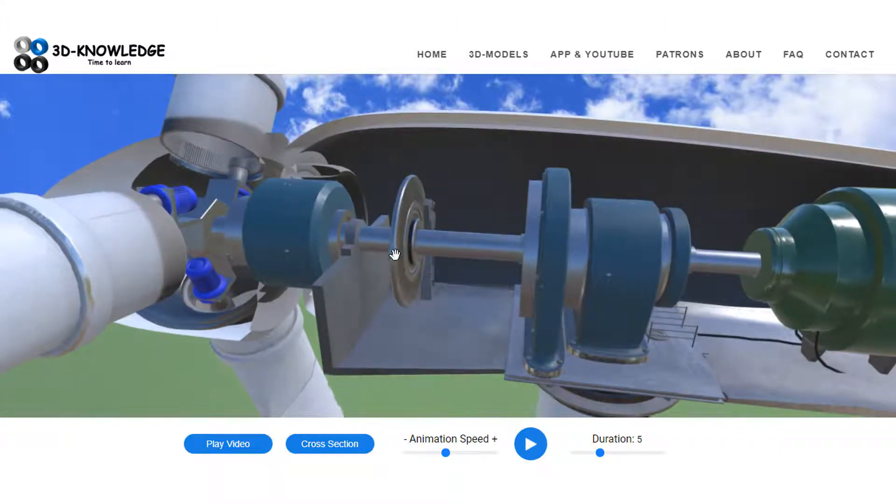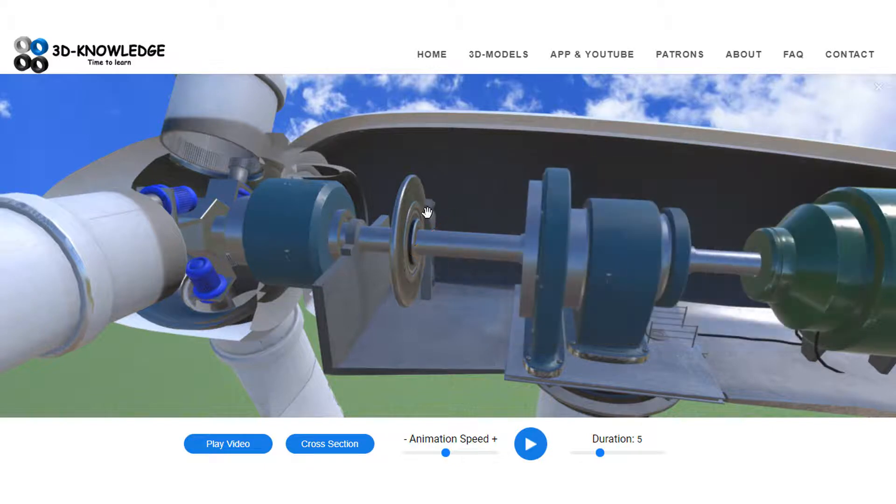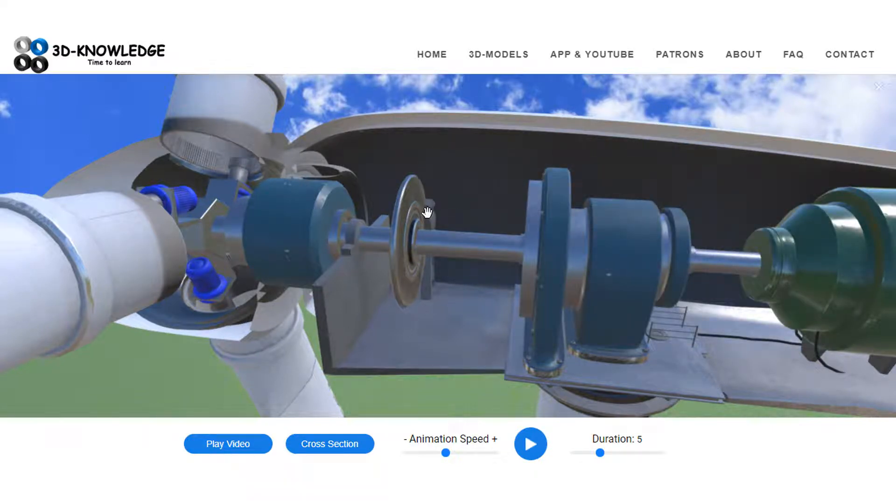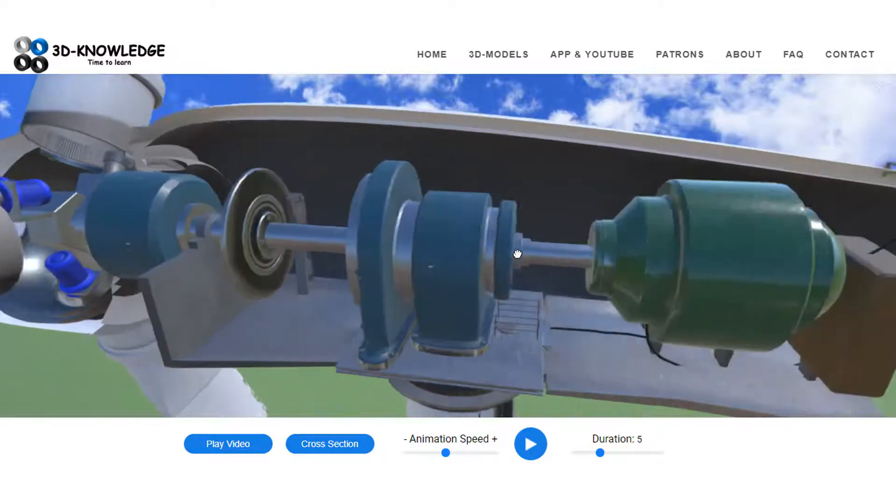So that main bearing will support the weight there. It will come through the nacelle housing and it will come to something called a hydraulic brake. Now the hydraulic brake's there to prevent the rotor turning. We can either do this generally just to stop the rotor turning, or we can do it in an emergency, so it's a very important piece of equipment.